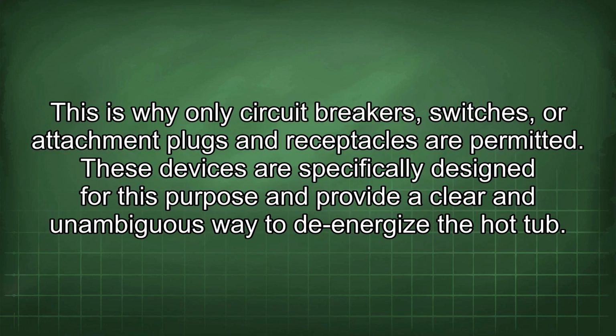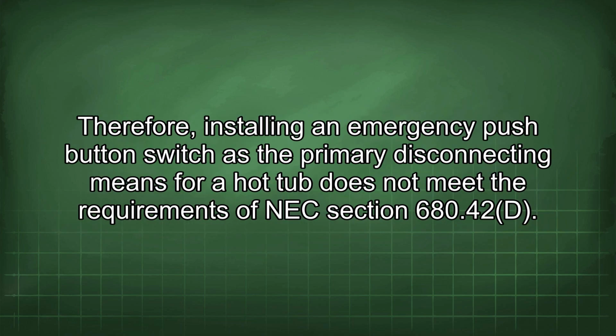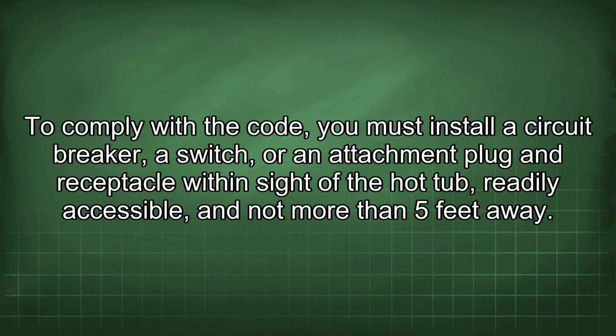This is why only circuit breakers, switches, or attachment plugs and receptacles are permitted. These devices are specifically designed for this purpose and provide a clear and unambiguous way to de-energize the hot tub. Therefore, installing an emergency push-button switch as the primary disconnecting means for a hot tub does not meet the requirements of NEC Section 680.42(D). To comply with the code, you must install a circuit breaker, a switch, or an attachment plug and receptacle within sight of the hot tub, readily accessible and not more than 5 feet away.